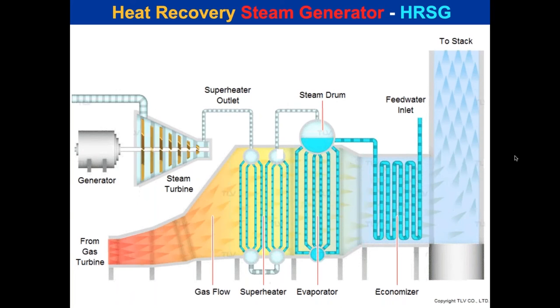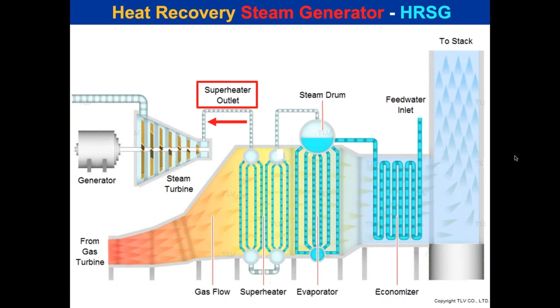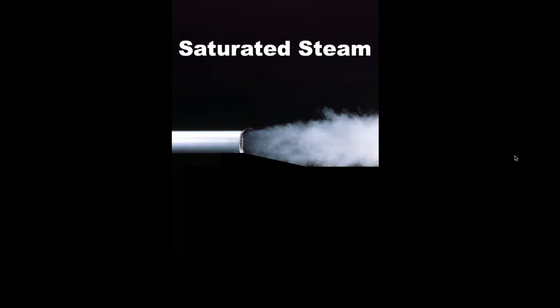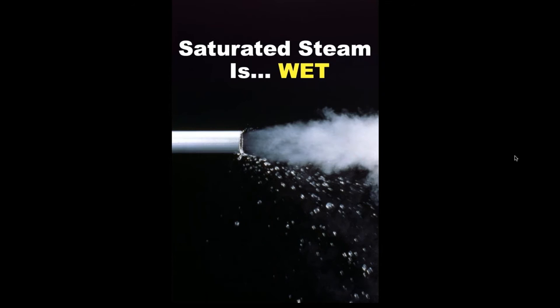A lot of you have what you call saturated steam, but you don't actually have saturated steam — never. What you have is wet steam. Steam leaves the boiler three to five percent wet. By the time it travels through your system, all of your steam, if it is not superheated, is wet steam at saturation temperature.